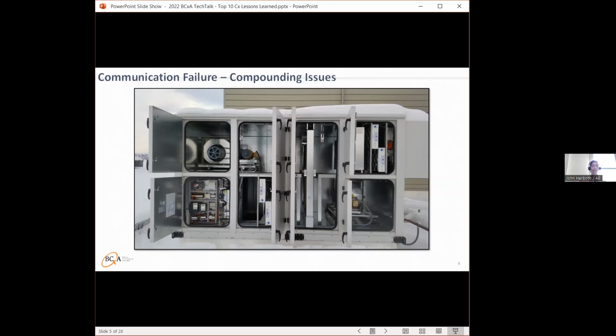Typically, when I go functional test a piece of equipment, I go through the safeties first - all the statuses, the equipment, smoke shutdowns, duct detectors, freeze stats. I check safeties whenever equipment is going to be operating or continually operating. That's the first thing I go after, because I want to make sure it shuts down properly on a high static or low static, and that equipment can't be damaged when we test it.